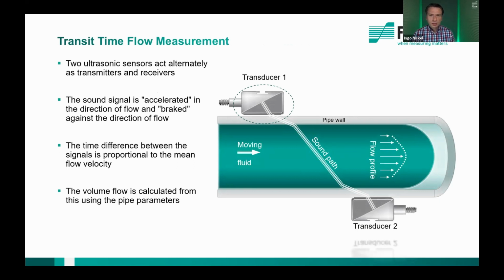For all of you who are not already familiar with this technology, I want to try to explain the measuring principle. In principle, it's a simple transit time measurement that we are doing with our equipment. We have at least two sensors, and these are mounted on the pipe, transducer 1 and transducer 2. These sensors send ultrasonic pulses through the fluid, and both transducers act alternately as transmitter and receiver. Due to the moving fluid, the signal travelling in flow direction will be accelerated, and the signal against the flow will be slowed down. The time difference between both signals is directly proportional to the flow velocity. And by multiplying the flow velocity with the cross-section area of the pipe, we can determine the volumetric flow.